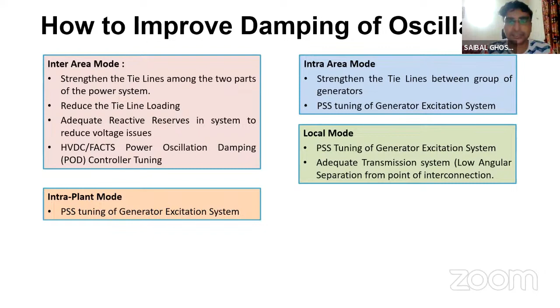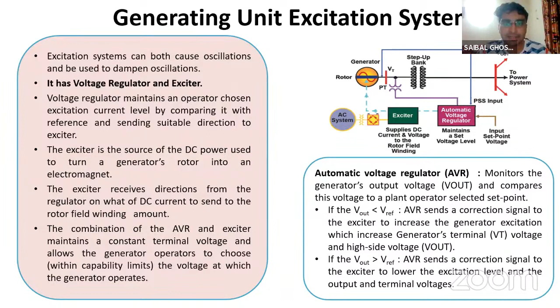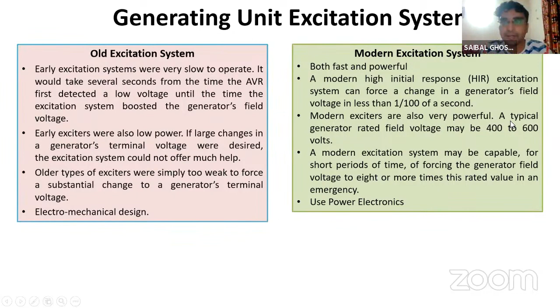So this is the overall schematic diagram of a generator. We know there are many kinds of excitation system. One could be brushless, one could be static. Static ones are very fast. They can provide a very high initial response, which in turn causes some small signal stability issues. At that time PSS comes into the picture and helps you improve the system damping. So these are the benefits of modern excitation systems.